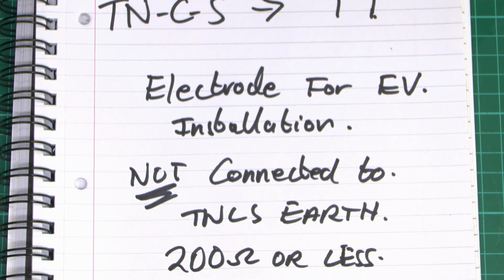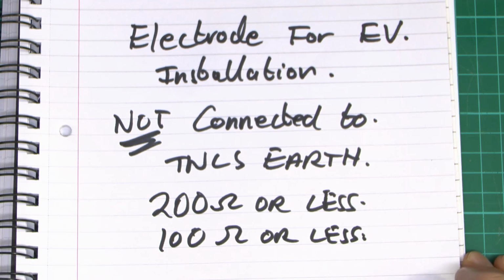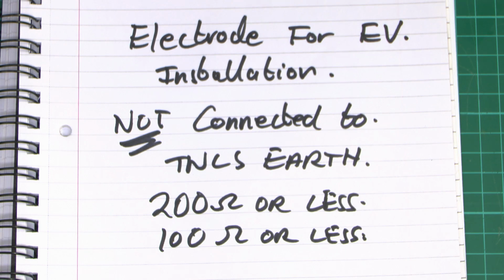depending on which set of books and guidance you actually read. So a standard electrode in the ground there. In most cases one is going to be sufficient, or if not you can also put two or more in, and as long as it's in the region of say 100 ohms or so, absolutely fine. And the crucial point is not to connect it to the existing supply's earth at all. You're then treating the installation of the charging equipment as completely separate and unrelated to whatever's coming into the building in terms of the earth provision.